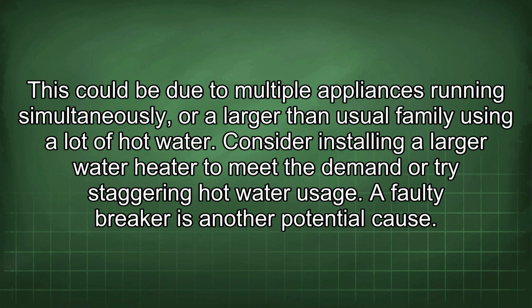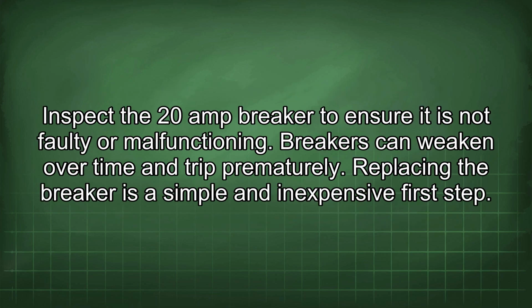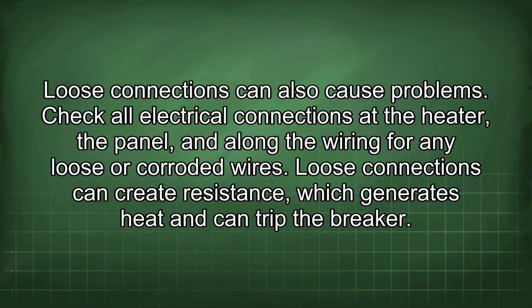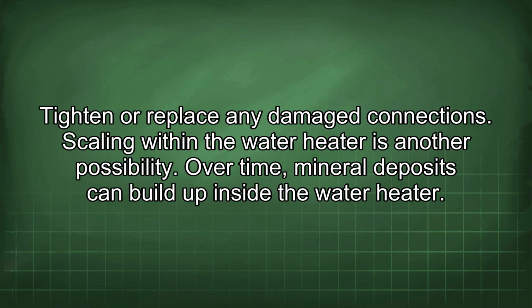A faulty breaker is another potential cause. Inspect the 20-amp breaker to ensure it is not faulty or malfunctioning. Breakers can weaken over time and trip prematurely. Replacing the breaker is a simple and inexpensive first step. Loose connections can also cause problems. Check all electrical connections at the heater, the panel, and along the wiring for any loose or corroded wires. Loose connections can create resistance, which generates heat and can trip the breaker. Tighten or replace any damaged connections.